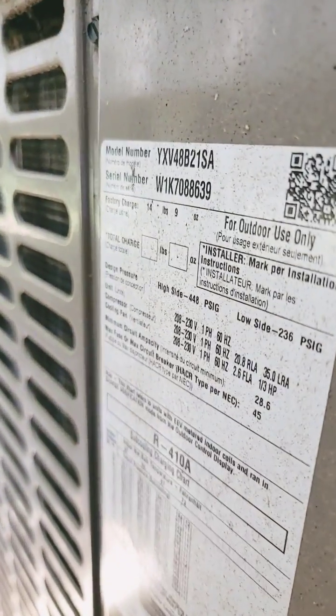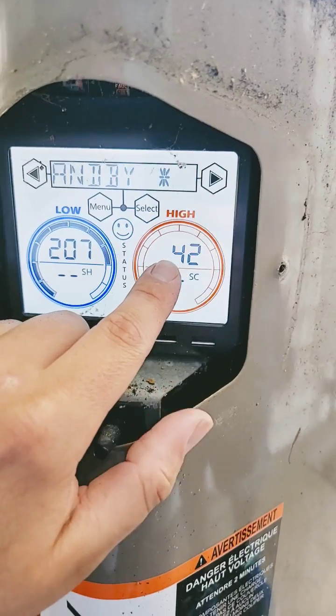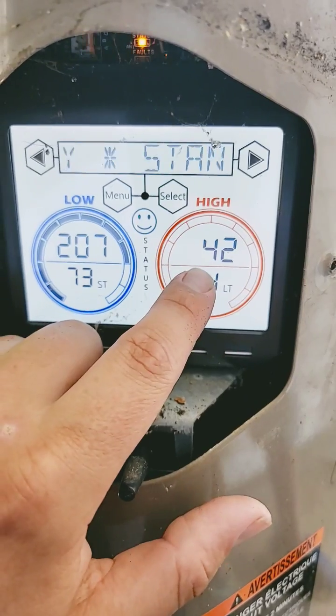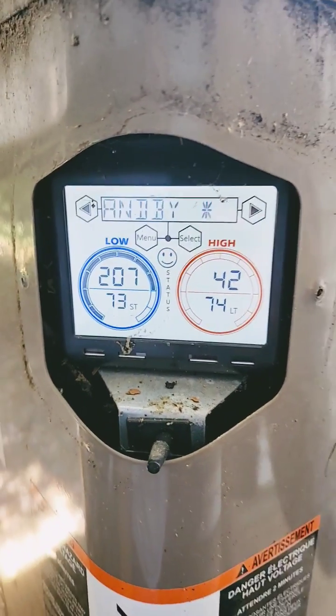If you ever work on one of these York YXV inverter outdoor units and you see that you have a weird pressure reading, check your transducers. There's no way the high side is 42 if the low side is 207. Let's take the panel off, I'll show you what's wrong.